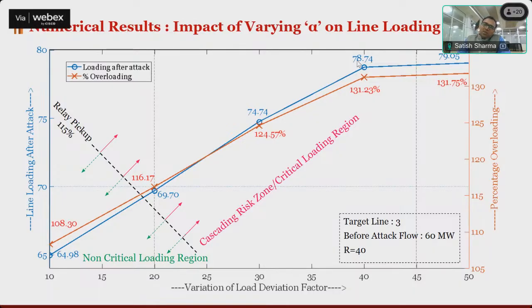Similarly, if you look at percentage overloading, with 10% deviation to a particular critical line, you are able to get 8.3% higher loading. Generally we keep relay settings up to something like 15% relay pickup. So if a line is overloaded by 15% more, the relay will trip. That threshold comes at a deviation in the load factor of around 20%. If 20% deviation is allowed, then we can go beyond the 15% relay pickup, and it is roughly 116.17 higher as compared to the 60 megawatt. So that's why this 69.70 megawatt as compared to the 60 megawatt. After that the relay will always trip.